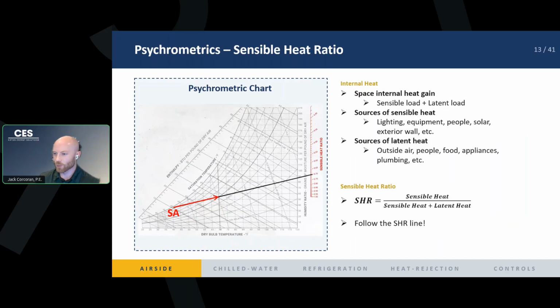If you had a greater sensible heat ratio than this, if it was closer to 1, you'd have less humidity in your space. Maybe you don't deliver your supply air that low. You know that the sensible heat ratio is going to drive you across horizontally. You can actually deliver your air at 50, or maybe 55 degrees Fahrenheit, because you don't have to overcome that extra latent load.